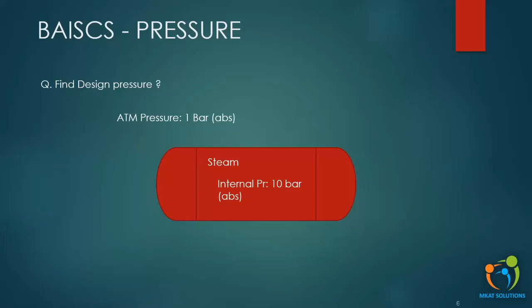So as a safety precaution, we design this vessel for external pressure of 1 bar also when there is a steam application. Understood? Either we design for external pressure or provide a vacuum relief valve, so that it will open and not allow the vacuum to be created. That is also one option. Correct? So we have to see the cost of both. If the vacuum relief valve provision is costlier, then we go for designing the thickness for external pressure. And if the thickness increase due to external pressure raises the cost way more than the cost of a vacuum relief valve, then we provide the relief valve. That is how these decisions are made.